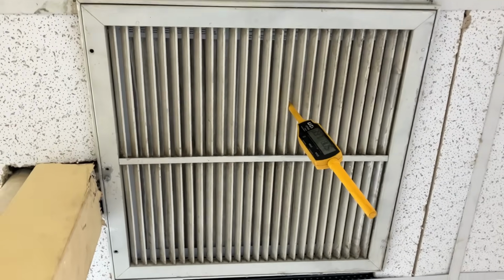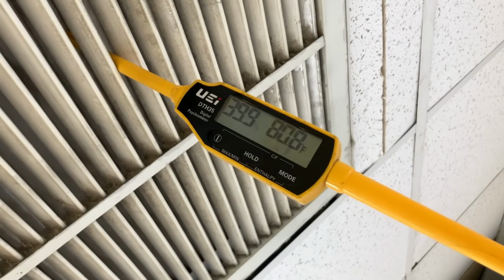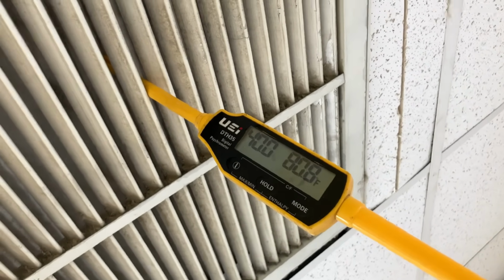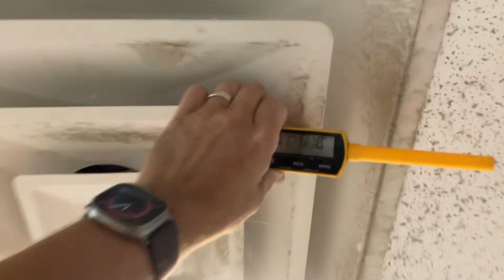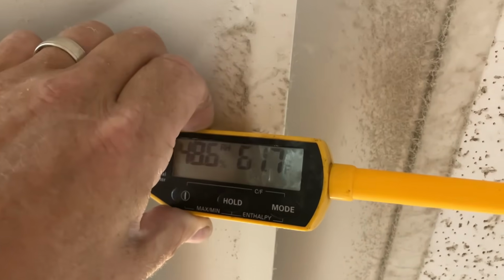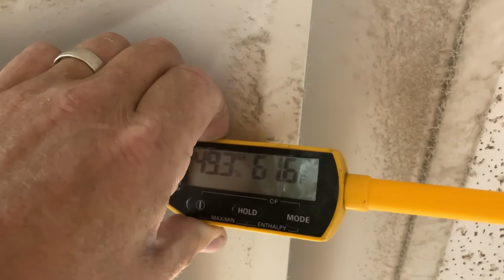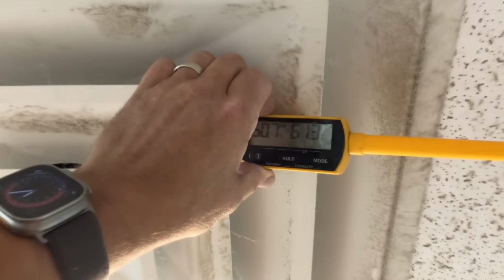All right, time for some temperature readings. 80-degree return, 61-degree supply. All right, one of the diffusers, almost 61.5 degrees here. Almost a 19-degree delta T.